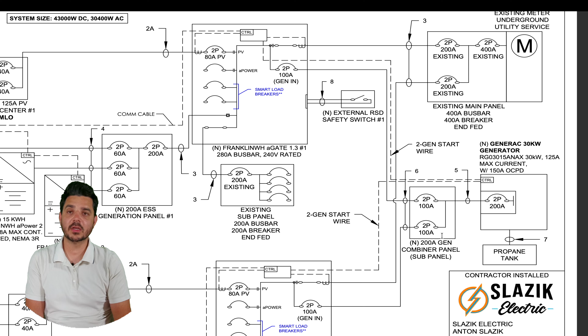So what's nice is that Franklin allows you to wire in both of them. So if one side of the site needs to turn on the generator, it can do that. And then through the relay, only that side of the site will receive backup power from the generator. If the other side needs it, then that one can enable it and also receive backup power from the generator. It's all stuff in the system configurations.